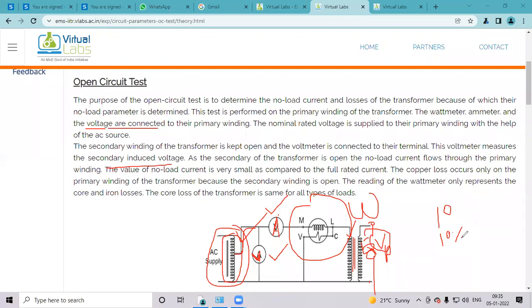The copper loss occurs only on the primary winding of the transformer because the secondary winding is open. Secondary winding is open, load current is 0, so secondary winding copper losses will be 0. Due to primary current, whatever copper losses occur in primary winding are according to formula I square R. So suppose primary current is 1 ampere and resistance of primary winding is 20 ohm. So 20 into 1 square is 20.